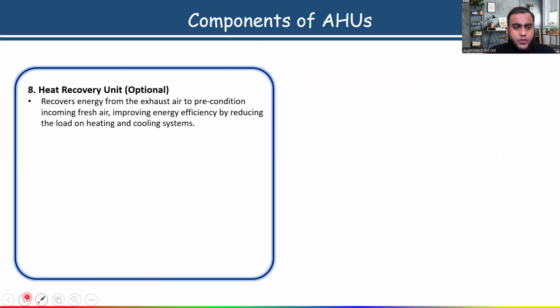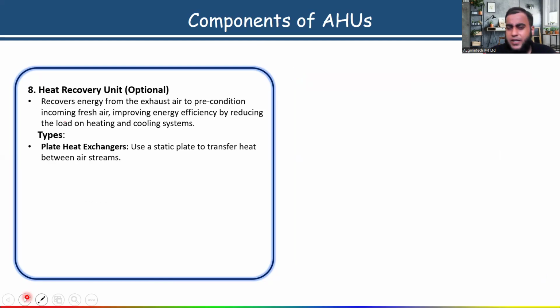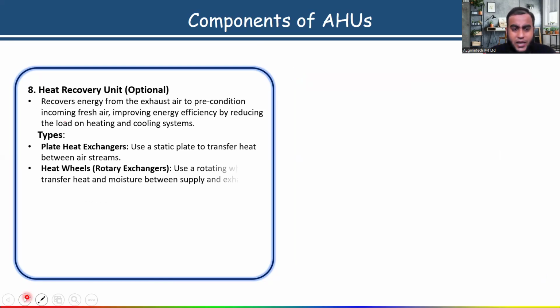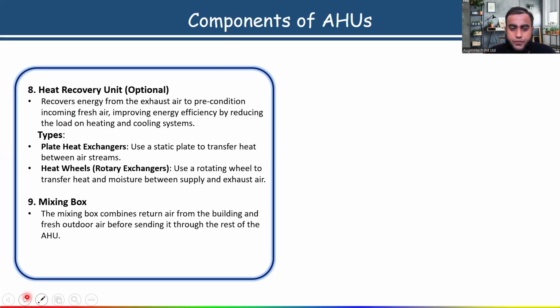Heat recovery unit recovers energy from the exhaust air to precondition incoming fresh air and improve energy efficiency by reducing the load on the heating and cooling system. Different types of heat recovery unit are given, like plate heat exchanger and heat wheels. Okay.